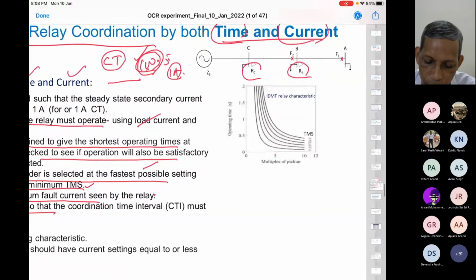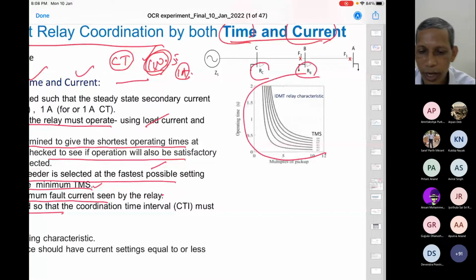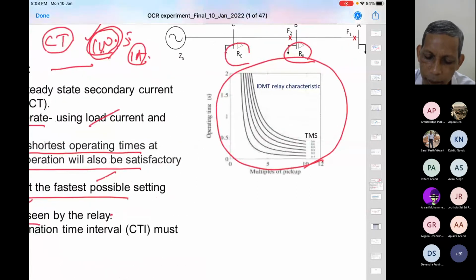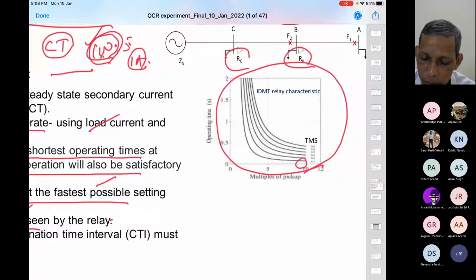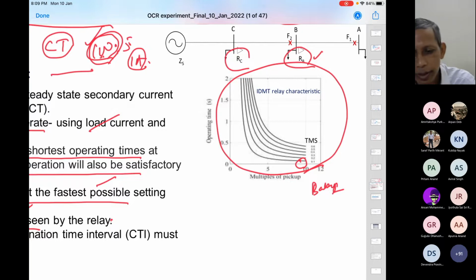Now, two important points. Suppose we have a set of IDMT curves available for the relay. Let us say we are talking about the IEEE inverse curve. In that case, the lowest curve is assigned to the extreme end relay, here RB. Then we go on adding, one curve after another, towards the source side, to provide for backup. Otherwise, you cannot do it. So that is the mechanism: the lowest curve is assigned to the extreme end relay, and then you go on adding up and up.